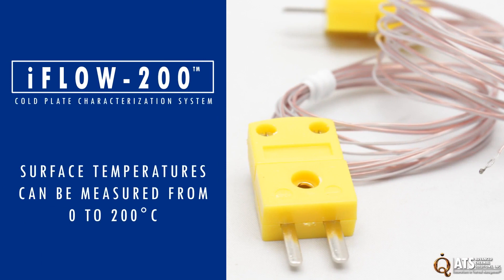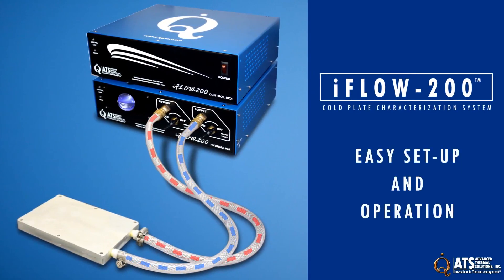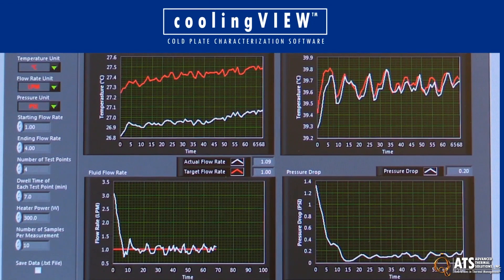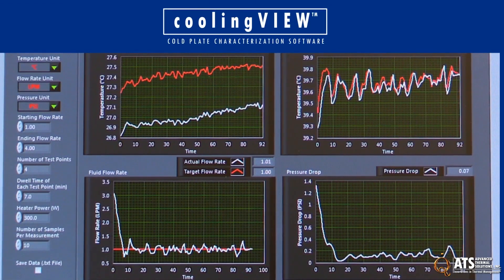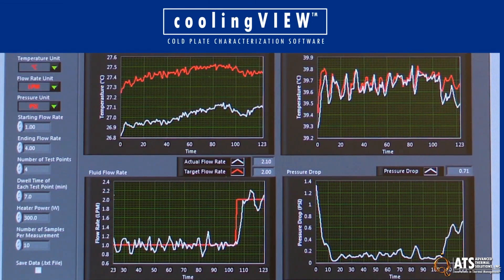Surface temperatures of the cold plate can be measured from 0 to 200 degrees Celsius using the system's two K-type thermocouples. The iFLOW-200 features easy setup and operation to save time when evaluating different cold plate models. It comes with CoolingView, a software which enables the user to run the system by simply setting the starting and ending coolant flow rates and choosing the dwell time, heater power, and other custom parameters.